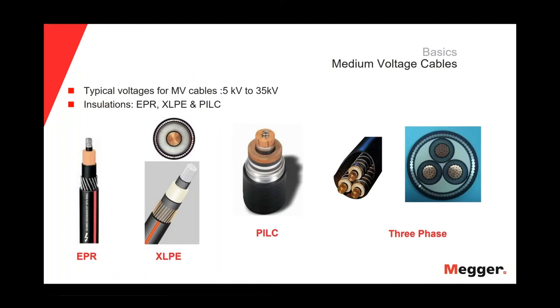talking of medium voltage cables, the typical voltage for medium voltage cables will go from 5 kV to 35 kV. We could say that the more typical voltages for medium voltage cables are 15 kV, 25 kV, and 35 kV. In terms of the insulation, we have what we call polymeric insulations, EPR and XLPE, and we also have the paper impregnated lead cables. In the first three pictures from the left of the slide, we can see the EPR, then the XLPE, and then the paper impregnated lead cable. All of them are in a single-phase configuration. The last two pictures on the right of the slide are a three-phase configuration.